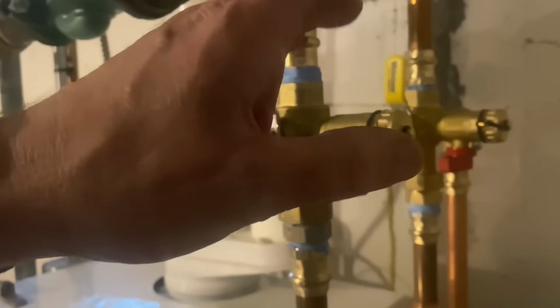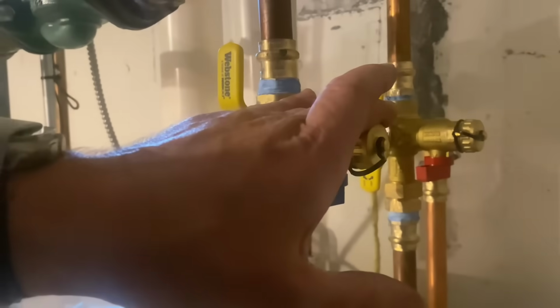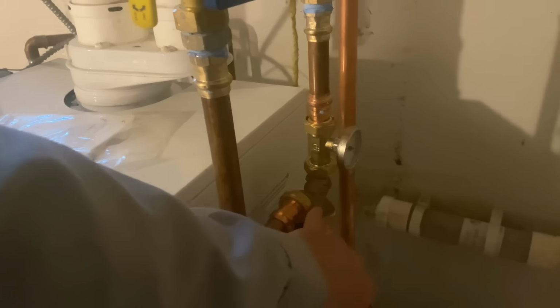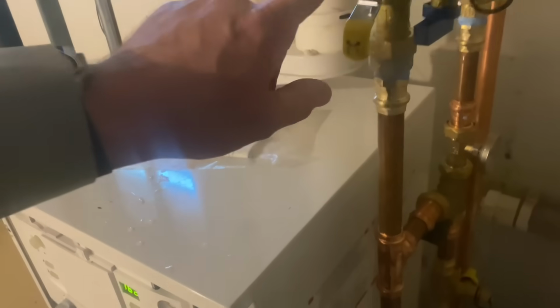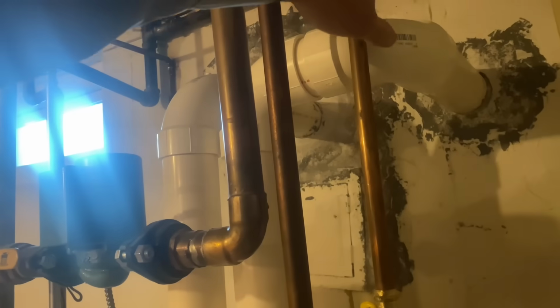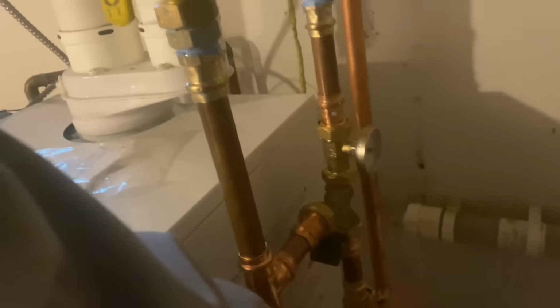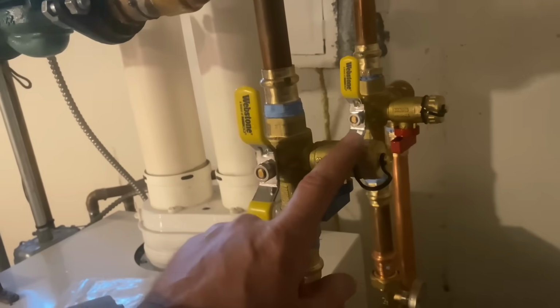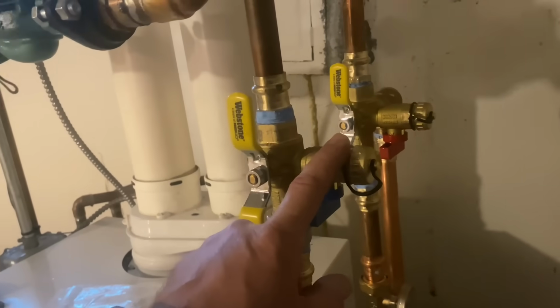So we have a problem internally with the unit. However, not wasteful, since when we hook up our flush setup to this inlet, this outlet, and the bucket and the pump, potentially going through the thermostatic mixing valve, we could flush through here, closing that directional valve, closing here, flushing chemical through here. As long as I close this valve, domestic hot water piping isn't disturbed. So close this, close this, close that. The pump with the bucket and the solution to the inlet, and the outlet back with a hose there.